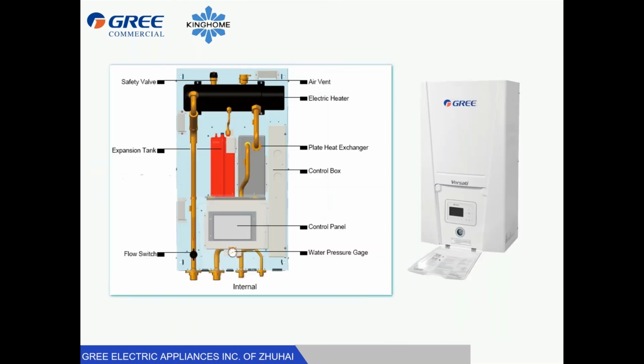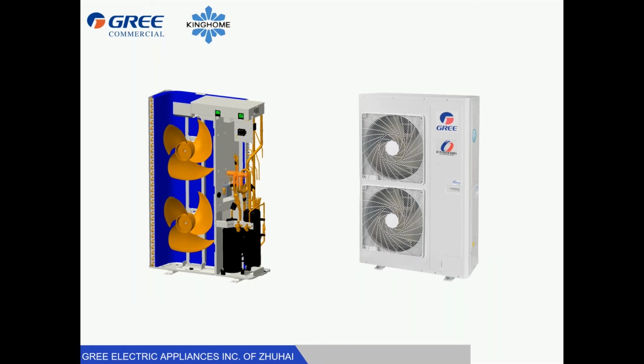Here's a cutaway view of the indoor unit. So you can see the plate heat exchanger in there and the expansion tank and also the electric auxiliary heat. So these units will operate down to -4 degrees ambient temperature. Below that, the electric auxiliary heat will kick in. Cutaway view of the outdoor unit. It's a pretty standard mini split outdoor unit. It does have an inverter compressor and electronic expansion valves.